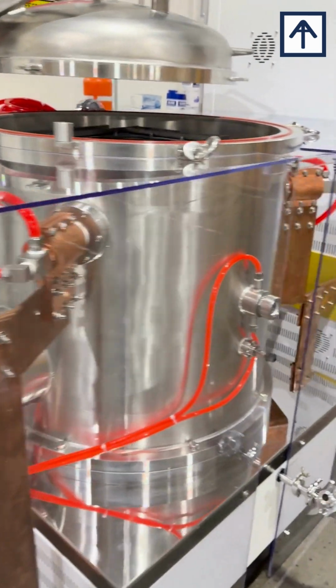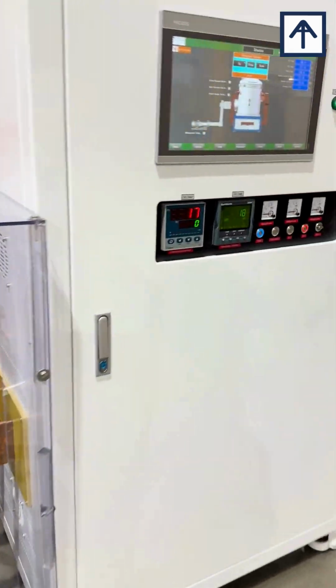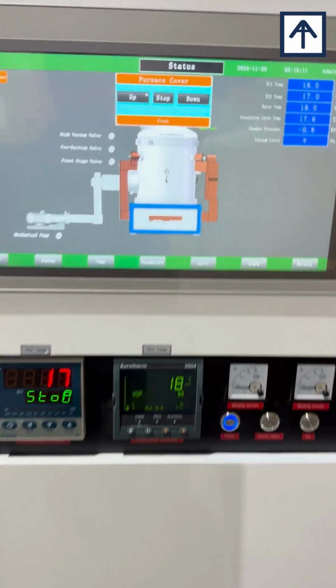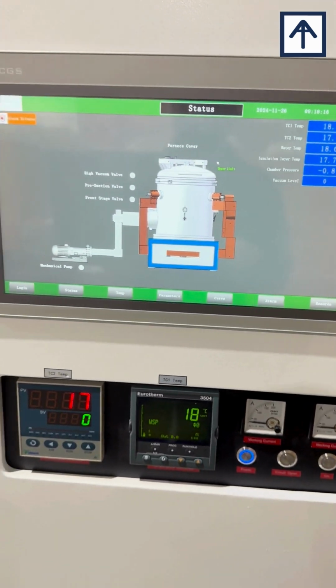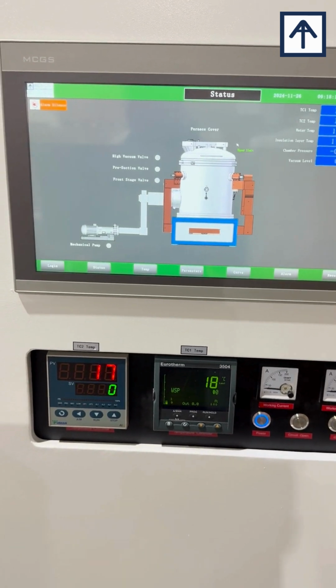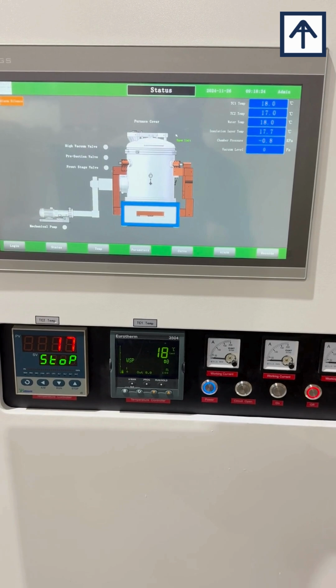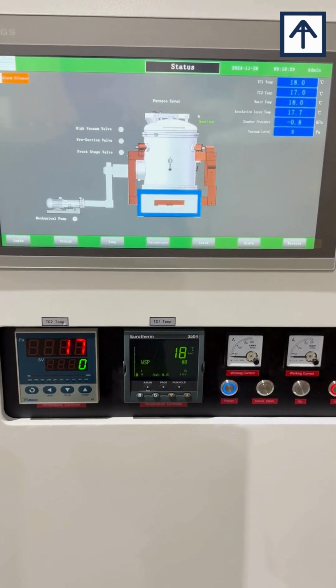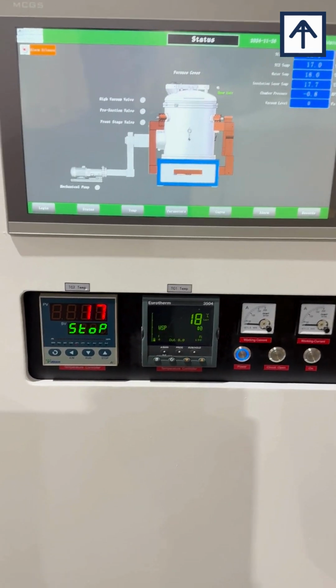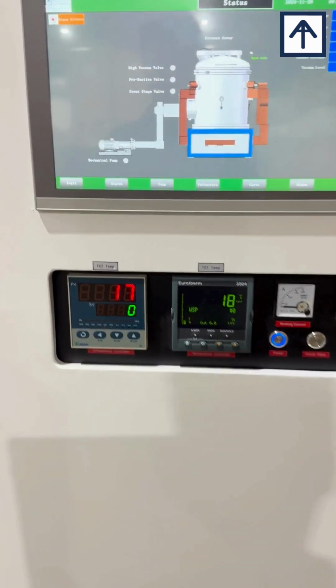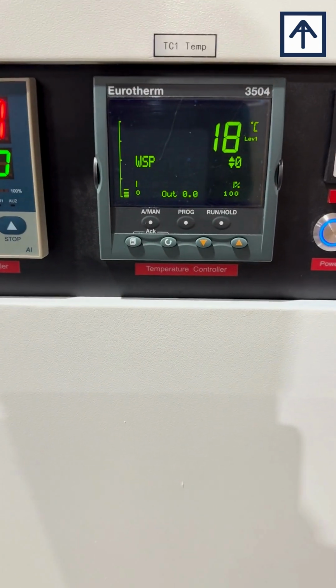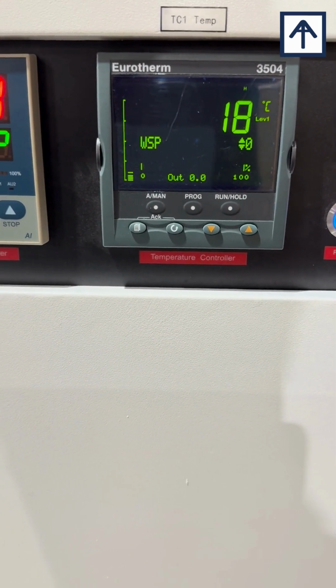The advanced digital temperature control features a touch screen, as you have seen on the electrical panel. This gives you access to look at the system status, temperature, put in the parameters for your system, and also get the graphs and curves and alarms and records for the system as well. The unit has a secondary Eurotherm 3504 controller, enabling seamless integration with an external PLC system.